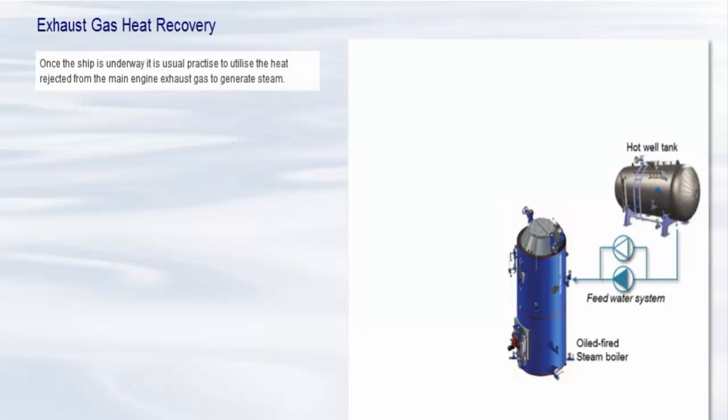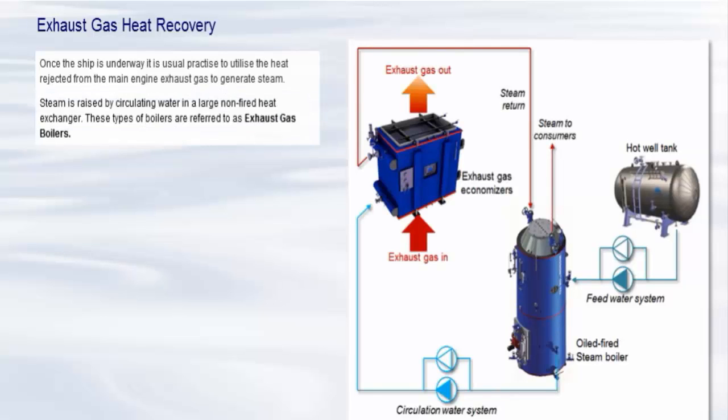Once the ship is underway, it is usual practice to utilize the heat rejected from the main engine exhaust gas to generate steam. This means that the boilers do not need to burn valuable fuel oil whilst at sea. Steam is raised by circulating water in a large non-fired heat exchanger. These types of boilers are referred to as exhaust gas boilers. The fired and non-fired boiler systems are usually interconnected.